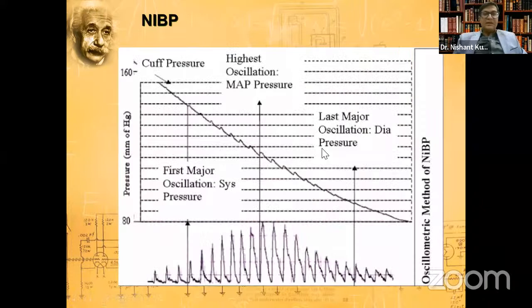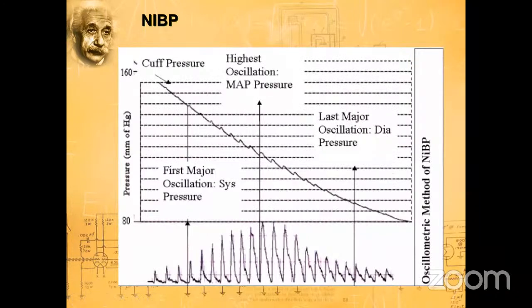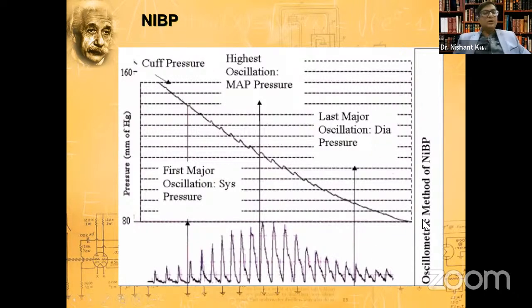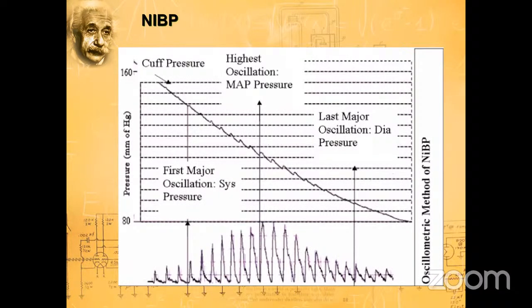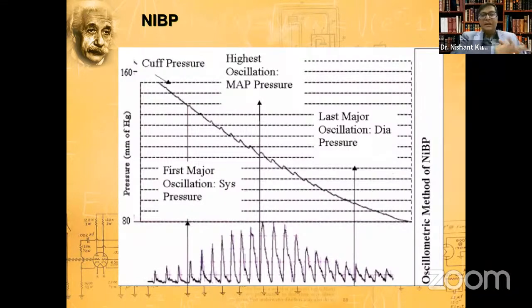A cuff is tied over the artery, and the most common site for blood pressure measurement is the brachial artery. That is why the cuff size and location have to be precise. Otherwise, we'll get a wrong reading. The machine pushes air into the cuff, it inflates. Now what will happen to the artery? As air goes in, the blood inside the artery will oscillate against the pressure being applied against the artery. So there's a measurement, there's a transducer. Sometimes it is in the cuff, sometimes it is in the machine itself.